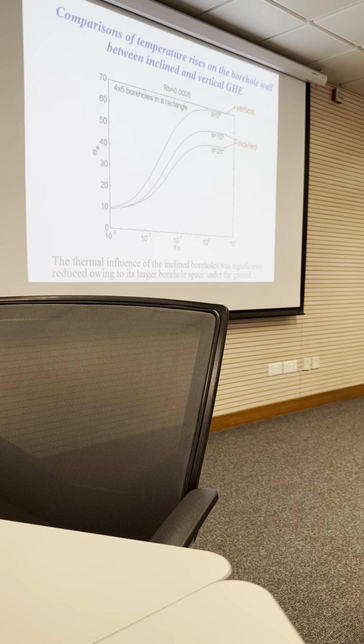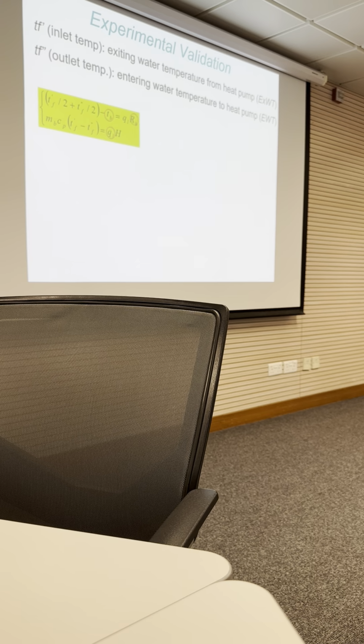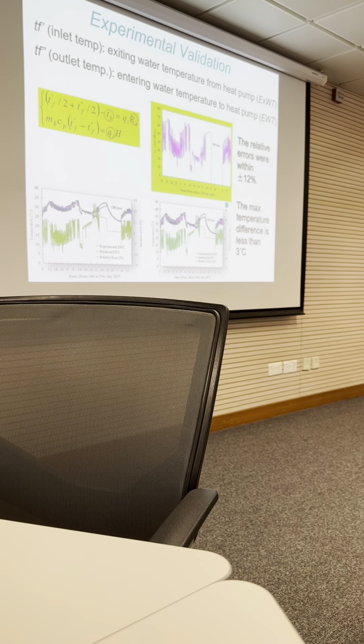You see the last sentence? The thermal influence of the inclined boreholes was significantly reduced owing to its larger borehole space under the ground. So inclined boreholes can solve partial problems, not all the problems, I must say. And we did an experiment with the test rig at the Ma Wan Park. The test rig is still there. There are 4 boreholes. You see, the relative error was within 12%. That's very good for such an engineering project.